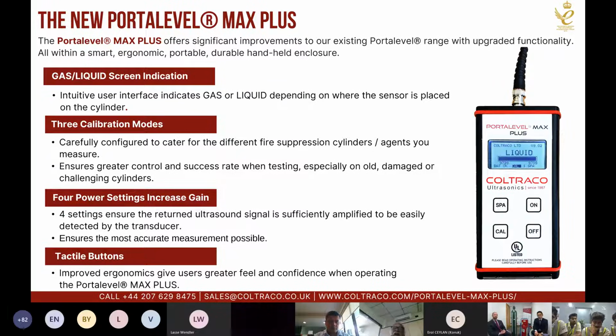These different calibration modes allow you to utilize the correct setting for your cylinders. It allows greater flexibility of working across different cylinder types. It has 4 different power settings to configure it so that it's suitable for cylinders of different conditions and different sizes. It ensures the most accurate measurement possible. And lastly, it has tactile buttons, so it feels ergonomic when you're using the equipment. The Portalevel Max Plus is also UL listed, so you can trust that the equipment is designed to be fit for purpose.